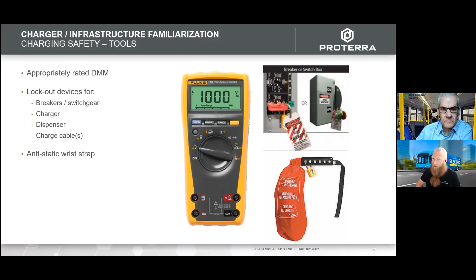You need to have a lockout device for the charger itself. That will be dictated by the procedures. You're going to need one for the dispenser, again dictated by the procedures. This also includes what's shown here as the lockout bag. Make sure you put that CCS cable, if you're working on a depot charging system, in that bag so that nobody can plug the CCS cable into the bus, thereby creating another path toward potential energy, which is your ESS, or energy storage system. Also make sure that you have your anti-static wrist strap. I know that isn't necessarily for lockout tagout, but if you're working in lockout tagout, it's good to have that on hand.